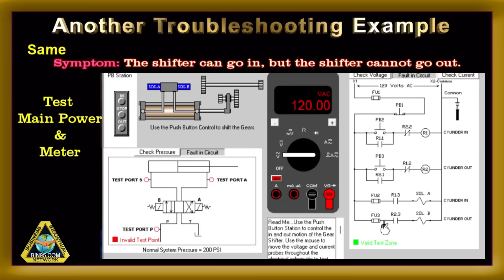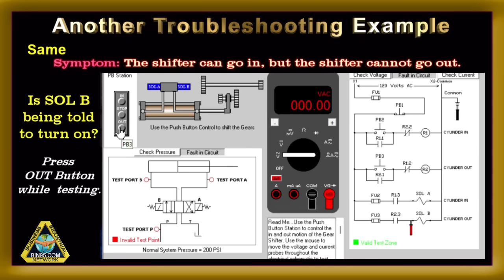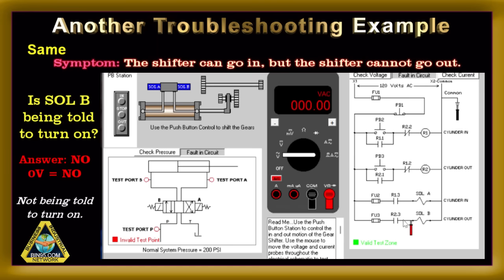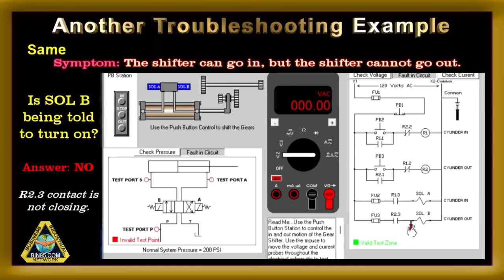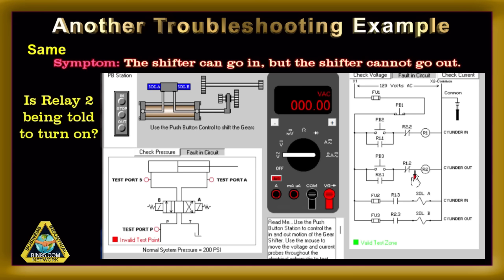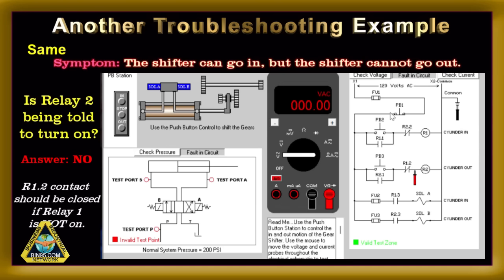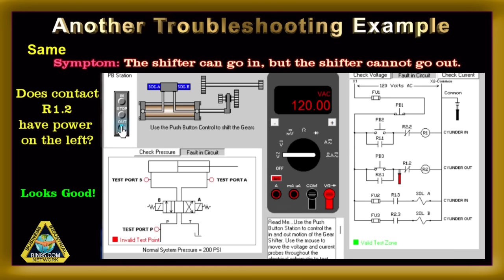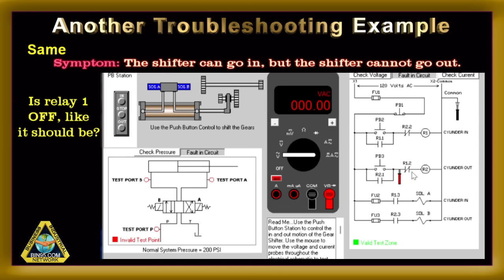Here is another troubleshooting example with the same symptoms but a different cause. Hint: it is not solenoid B this time. Next, see if solenoid B is energized — press the OUT button while testing for voltage. No voltage here. Next, check the left side of R1.2 for voltage while the OUT push button is pressed. It should be 120 volts.